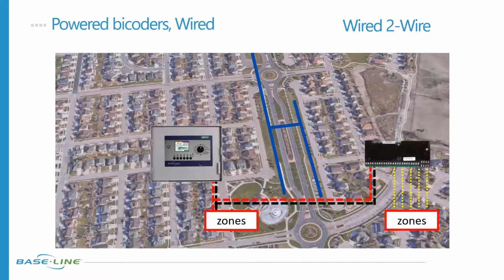So that powered bicoder we saw earlier is just another 2-wire device on that wire path. Some of the cool things about this: it works with either controller, there's no networking involved, and it works really well when you have an existing wire path or a new 2-wire path you can bring in. This allows you to bring devices back into that controller, but in a wired method.